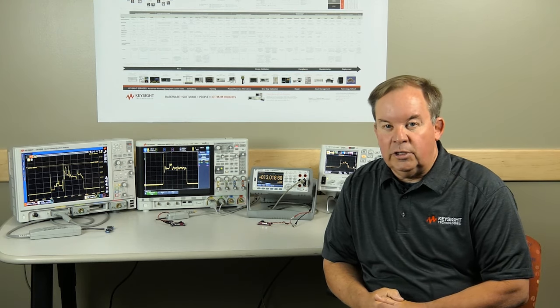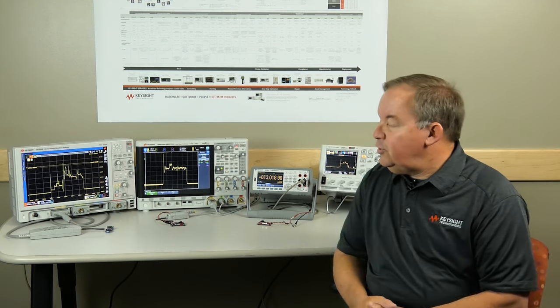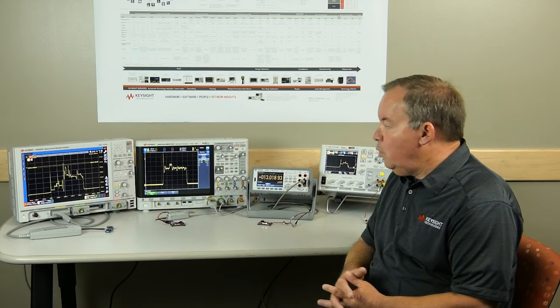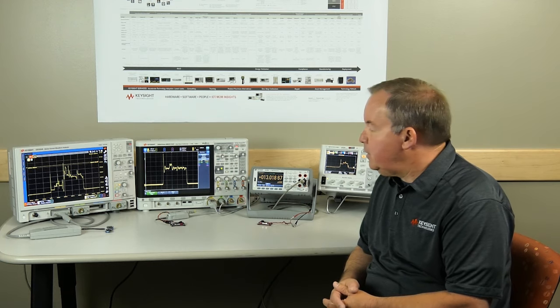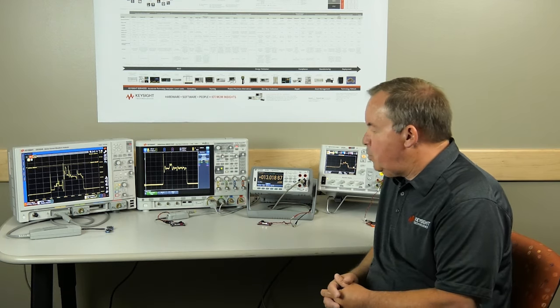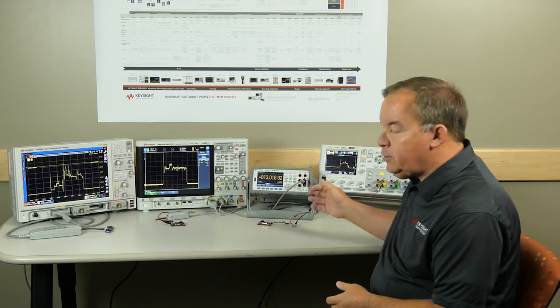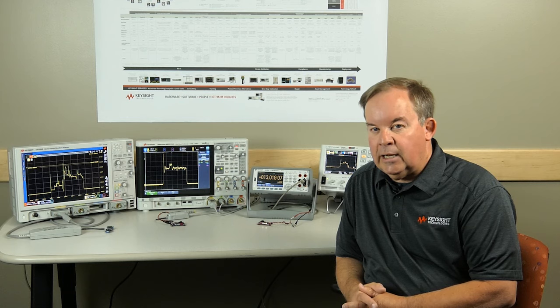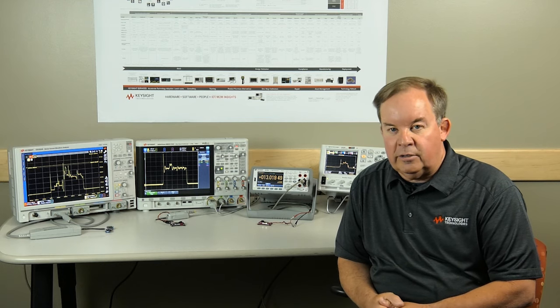Keysight offers a number of solutions available to attack this problem in different ways. As you can see behind me, we have a device current waveform analyzer with a typical pattern from a wearable device as a device under test. We also have an oscilloscope, which may already be on your bench, using a current probe to measure those waveforms and quantify the problem. We have a traditional DMM, and finally a DC power analyzer, purpose-made for this job.